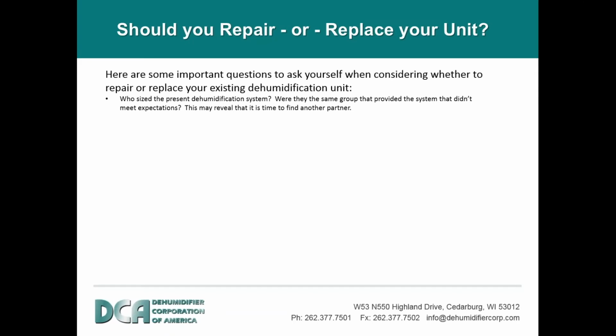Another thing, did they supply an oversized unit to fulfill other project needs, such as pool water heating or additional cooling requirements? Dehumidifiers can do many things. Of course, the primary function is to control the relative humidity, while at the same time they're adding pool room heat to heat the space, and of course in cold climates this is all very welcome. Now many times pool room dehumidifiers also have the pool water heating feature which assists in pool water heating. Many times it's not needed. We look at small pools, residential pools under 500 or 600 square feet, as this is a feature that really is not needed, and certainly in small hotel or motel pools as well. Because even though your system has pool water heating assist, you still need a primary pool water heater. So it's a redundant system at that point.